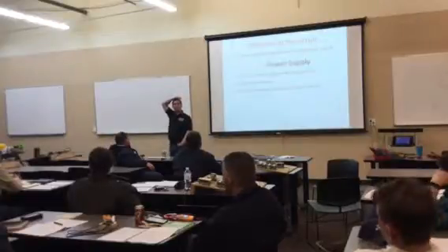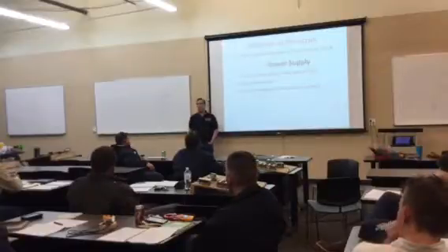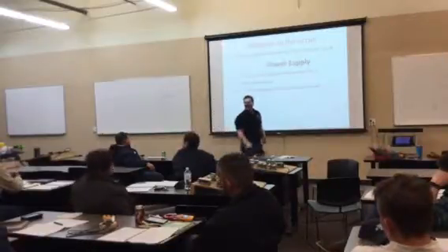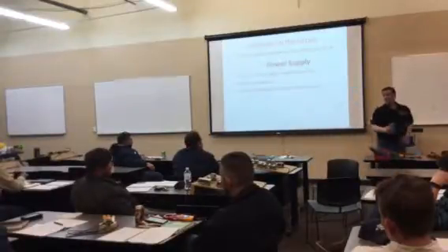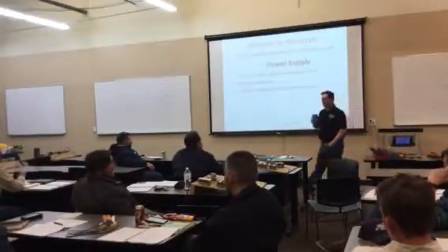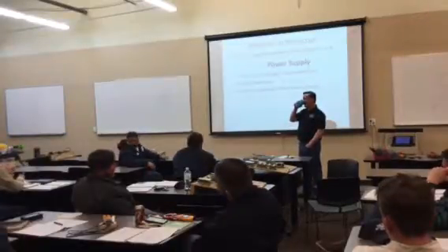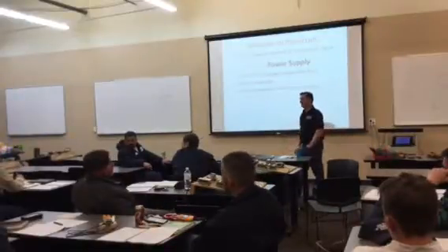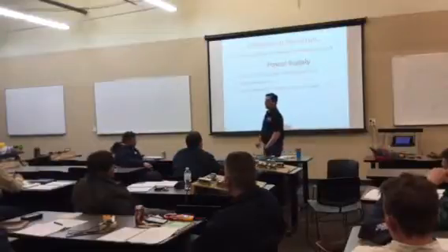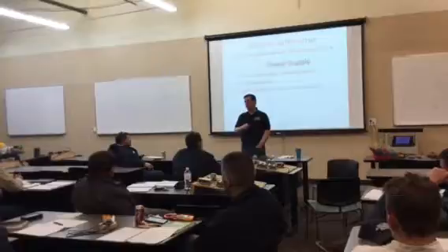So for example, that's a common one we get on the plumbing side. Oh, I want to go to electric tankless. Well, electric tankless, the average house is not equipped with the sizing for that power. You can do either so many amps on single phase or fewer amps on 3-phase, but a lot of the time they don't have that availability because the average amperage for those is 80 amps, and the house is already being used for that amount.